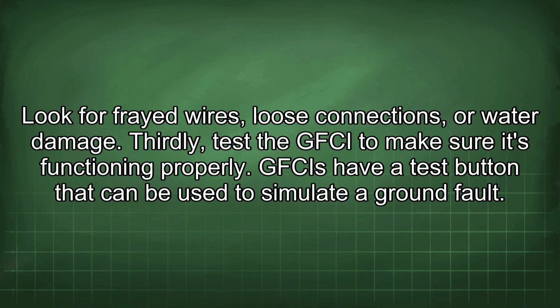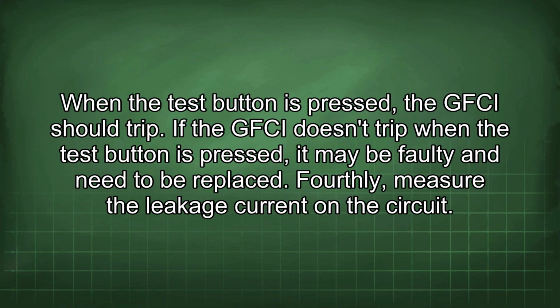Thirdly, test the GFCI to make sure it's functioning properly. GFCIs have a test button that can be used to simulate a ground fault. When the test button is pressed, the GFCI should trip. If the GFCI doesn't trip when the test button is pressed, it may be faulty and need to be replaced.